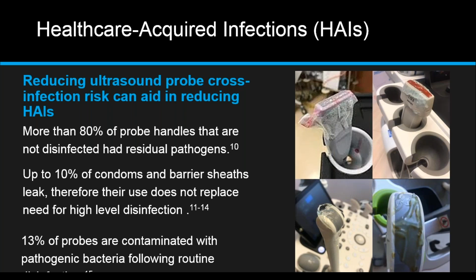So I want to repeat that. The use of a condom sheath or barrier does not eliminate the need for high-level disinfection because those are not perfect protection. 13% of probes are contaminated with pathogenic bacteria following routine low-level disinfection.